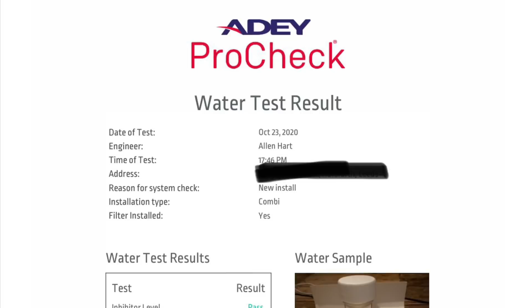I do a water test on all my jobs now. I test the water in front of the customer, and it's dated and timed so you know it's correct. With the ADEY app, you take a picture and it sends that to the customer in an email, so they've got proof the boiler was installed correctly, and there's no manufacturers getting out of warranties.